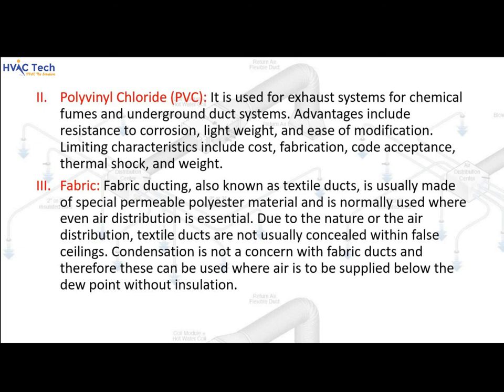Fabric ducting, also known as textile ducts, is usually made of special permeable polyester material and is normally used where even air distribution is essential. Textile ducts are not usually concealed within false ceilings. Condensation is not a concern with fabric ducts; therefore, these can be used where air is to be supplied below the dew point without insulation.